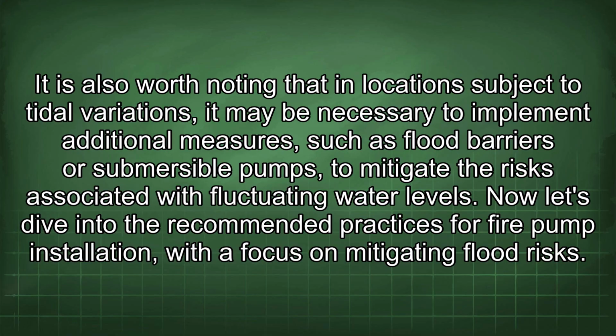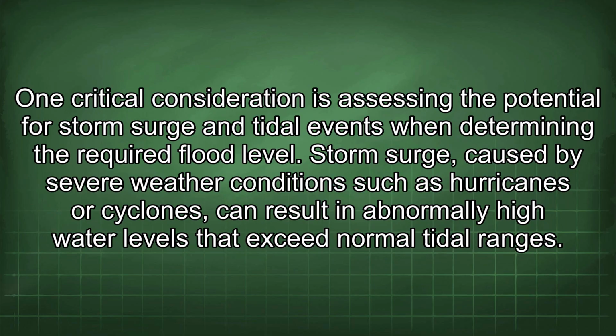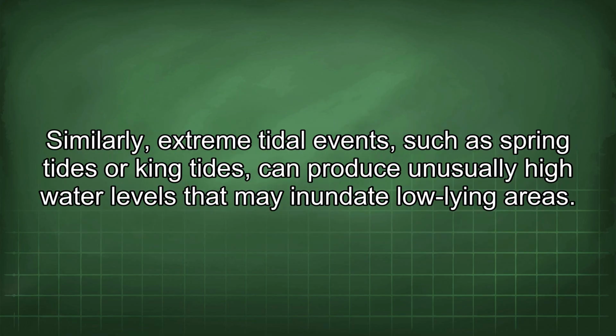Now let's dive into the recommended practices for fire pump installation with a focus on mitigating flood risks. One critical consideration is assessing the potential for storm surge and tidal events when determining the required flood level. Storm surge caused by severe weather conditions such as hurricanes or cyclones can result in abnormally high water levels that exceed normal tidal ranges. Similarly, extreme tidal events, such as spring tides or king tides, can produce unusually high water levels that may inundate low-lying areas.